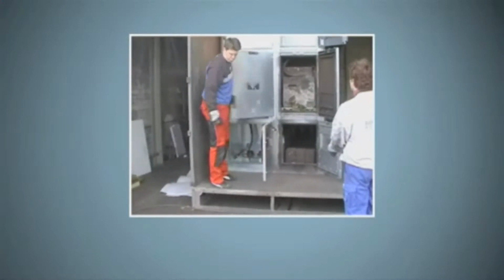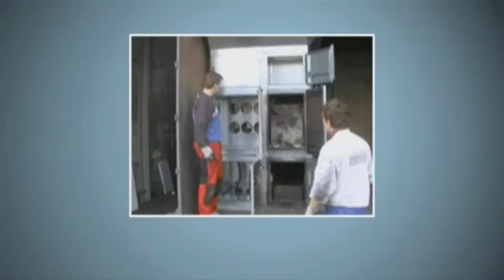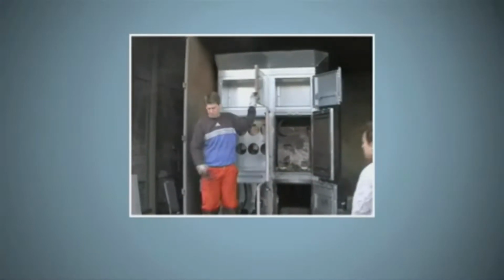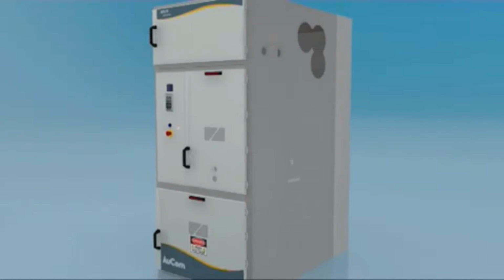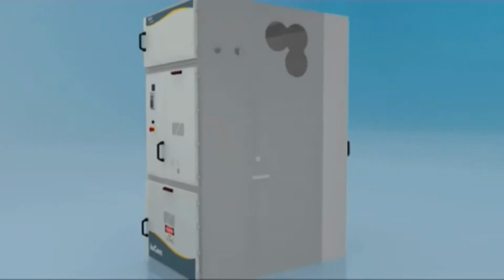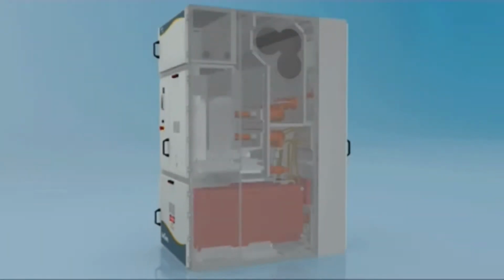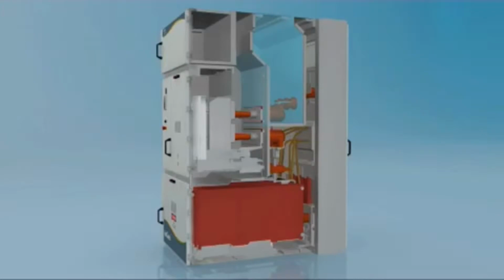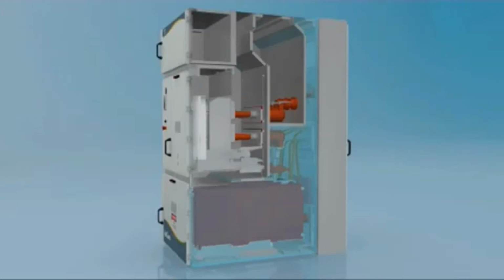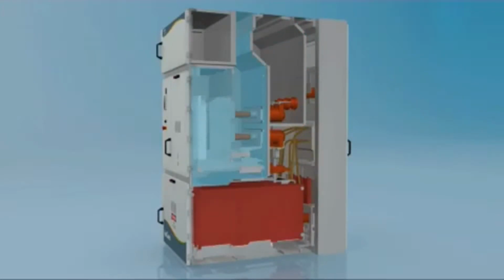The compartment sidewalls protect LV sections from an arc fault in the MV section and would have protected any operators from harm. MVX L series panels have 3 power compartments and 2 LV compartments: the bus bar compartment, the cable compartment, the circuit breaker compartment, and 2 instrument compartments.